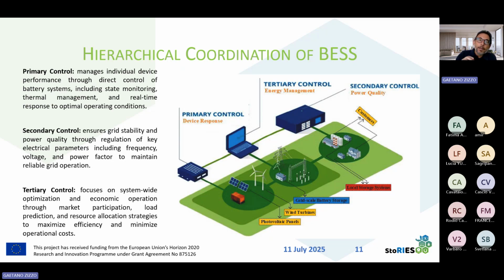Usually, the hierarchical coordination of batteries presents three control layers. A primary control that is devoted to managing the individual device, the individual storage performance, through a direct control of the battery systems, and that includes state monitoring, thermal management, and real-time response to optimal operating conditions. This is the primary control. It only focuses on the single unit.